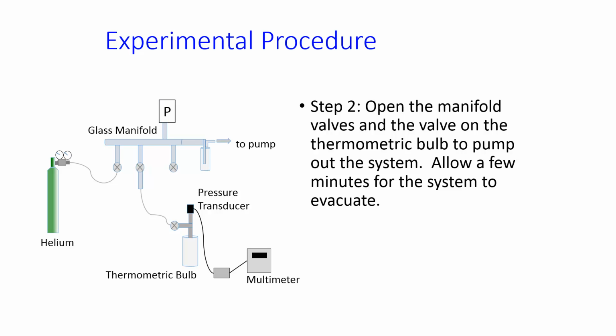Once the pump is turned on, you're going to need to evacuate your whole system. Any air in the system is going to give you bad results. So you'll close the helium tank, open all the other valves except those that aren't attached to anything, and pump on all of the system. You want to wait a few minutes because pumping efficiency goes down as pressure goes down, so it's harder to get the last little bit of air out of the system.